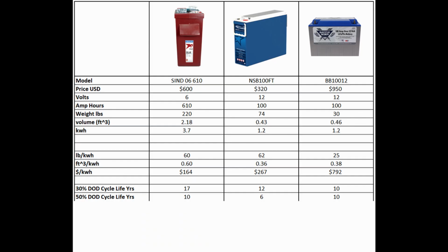Later on, we'll talk about some practical aspects of the technologies where lithium does have some significant benefits, but in the meantime, let's see if lithium can redeem itself as we continue this analysis. If we run the same exercise at 50% depth of discharge every day, 365 days per year, which is extremely aggressive and few applications achieve or require this, remember this is every single day, 50%, then the results change a little and lithium and flooded are about on par in terms of life. AGM starts lagging behind. Still, per dollar spent, it still doesn't win. Flooded lead acid gets 10 years, AGM 6, and lithium still gets 10.